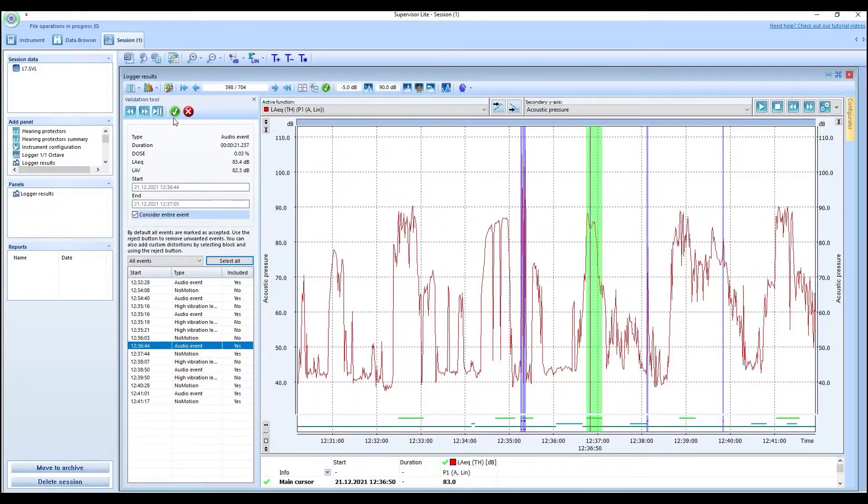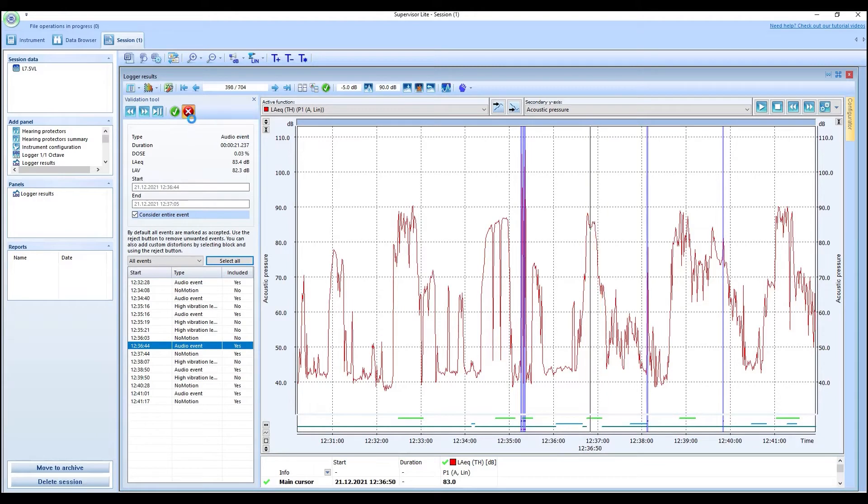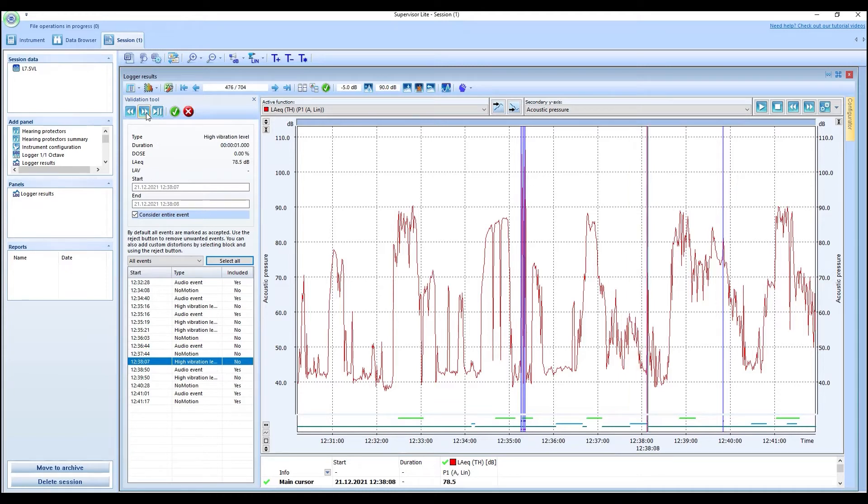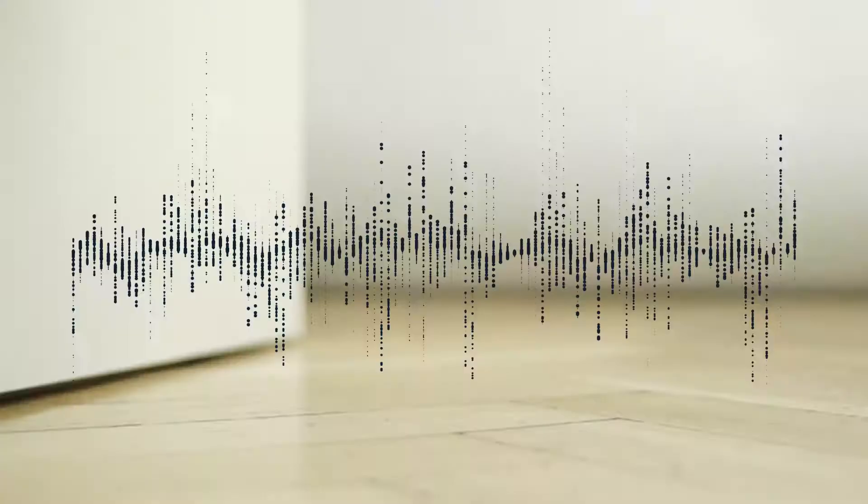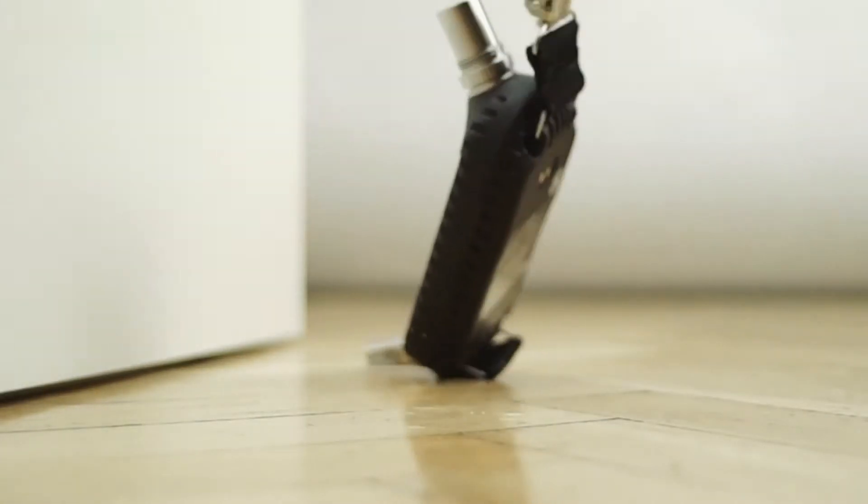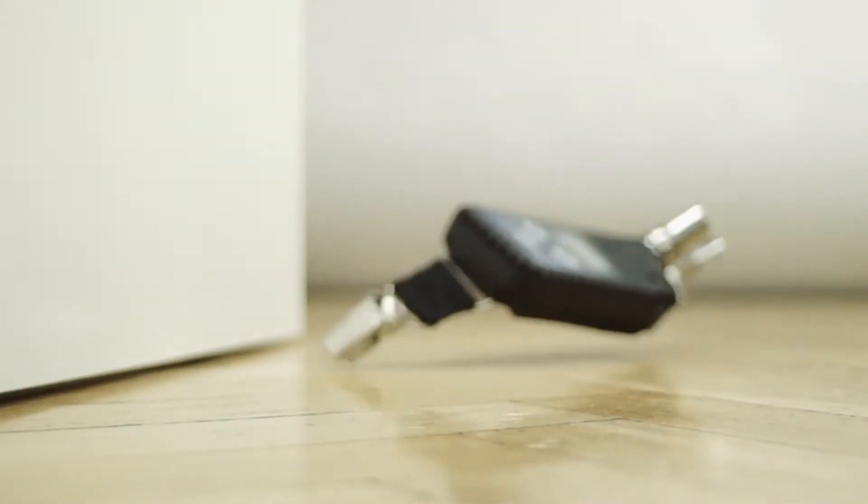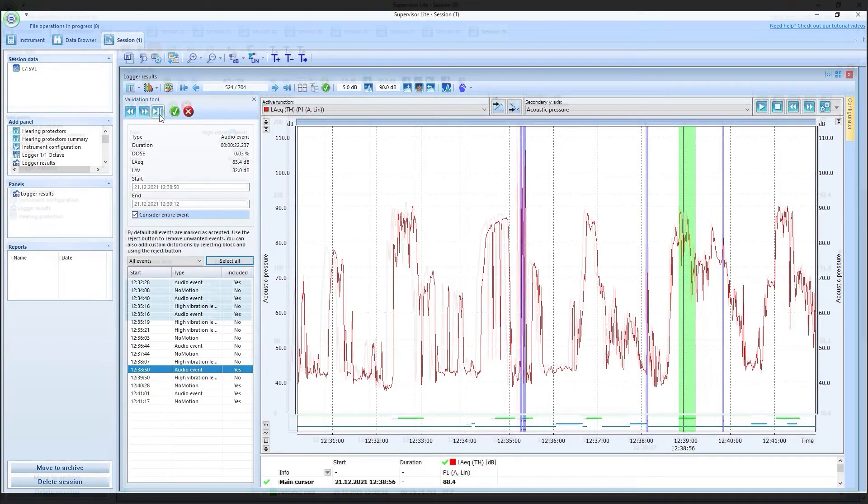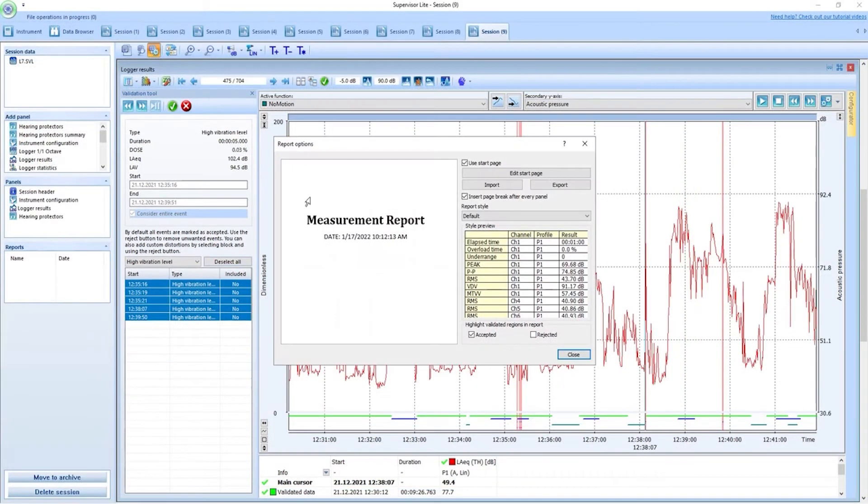Supervisor Lite introduces a new function, the validation tool. A module that allows for fast and easy validation of results by removing erroneous data such as invalid noise sources, mechanical shocks to the instrument interpreted as acoustic impulses, and data gathered when the dosimeter wasn't properly worn.